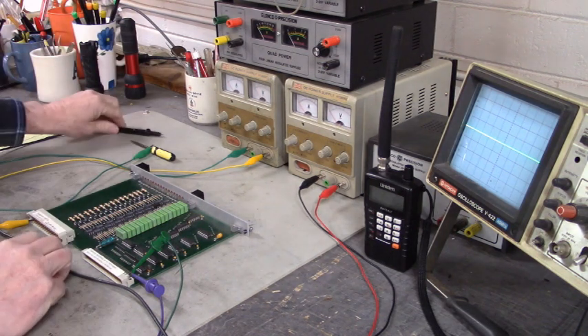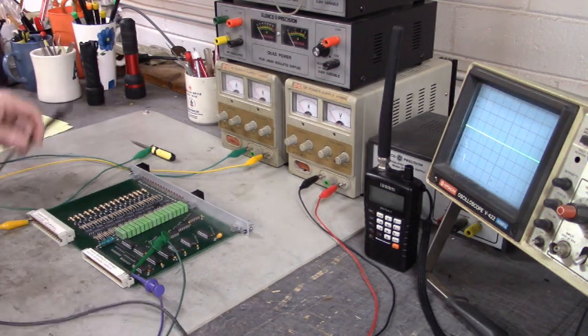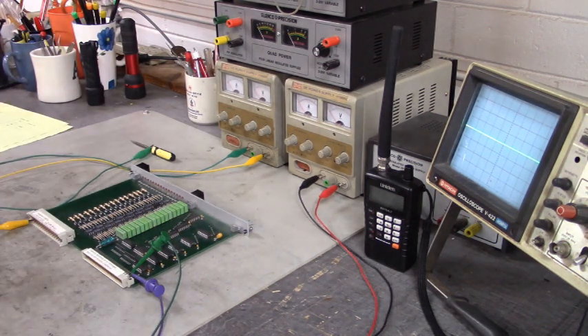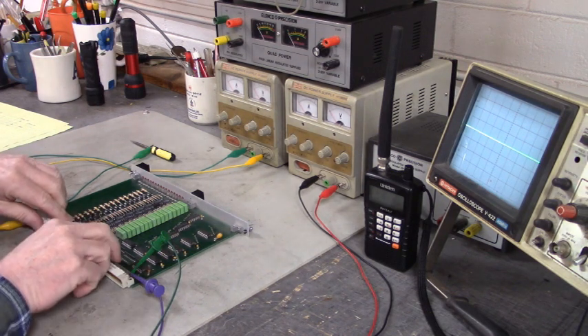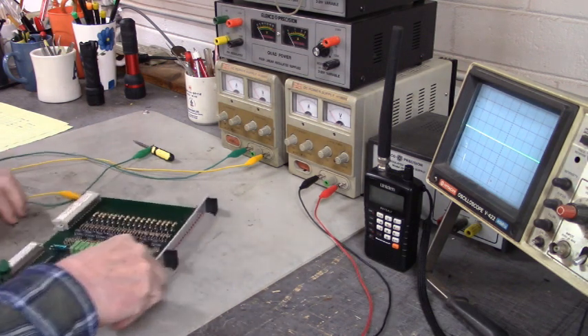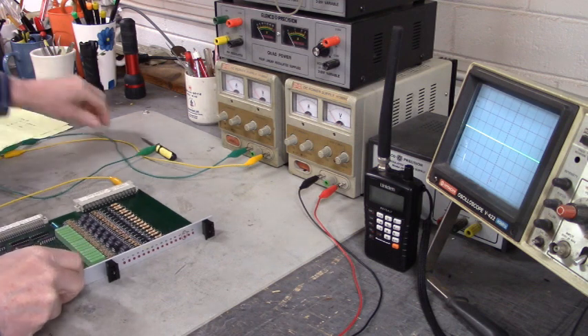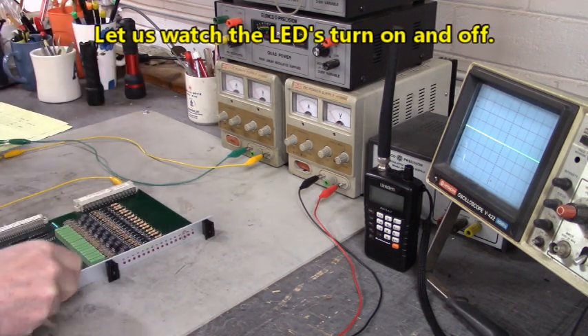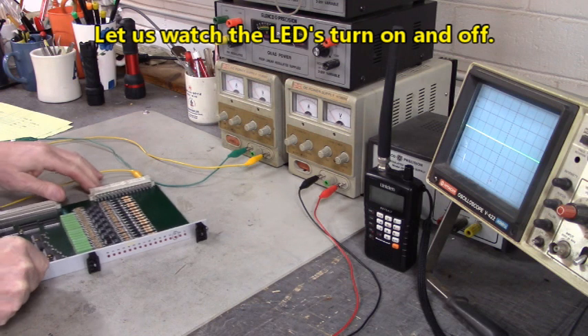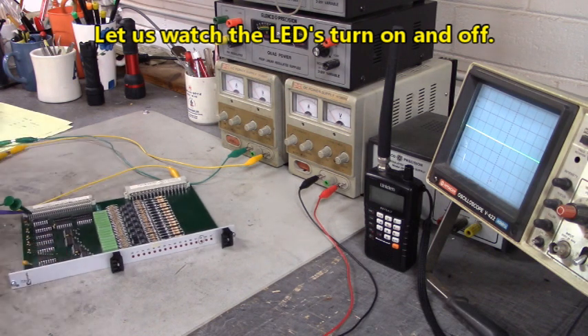Now, what we're going to do, we're going to move the card around and we'll look at the LEDs. We'll look at the LEDs turning off and on when I probe those optocoupler inputs.